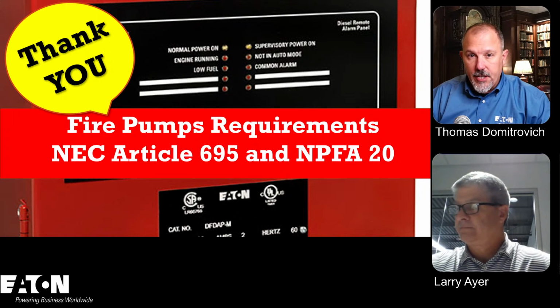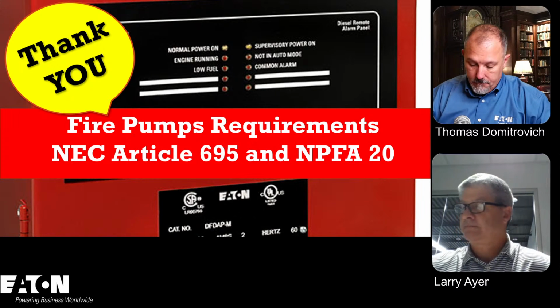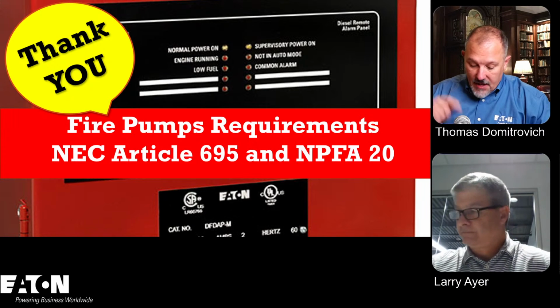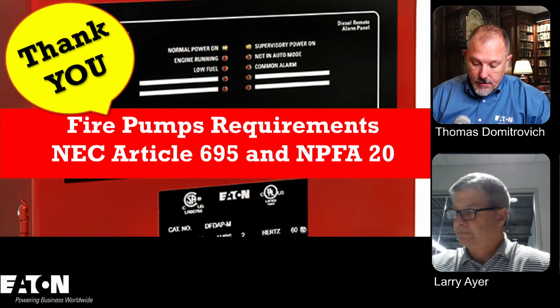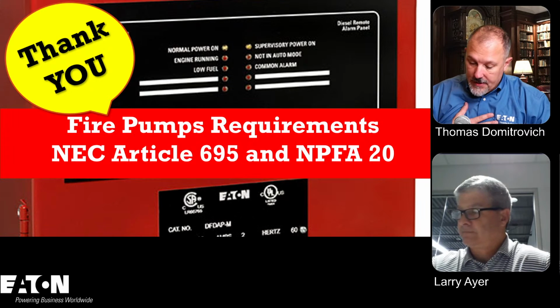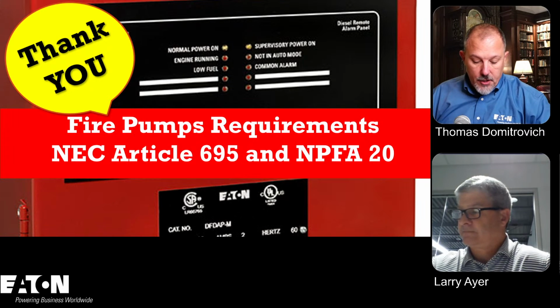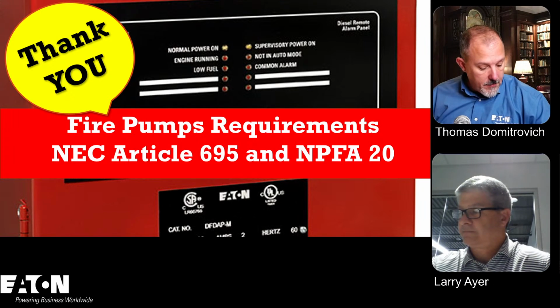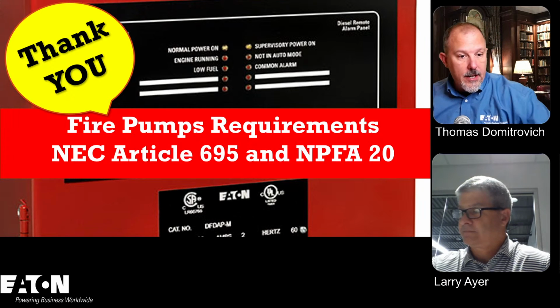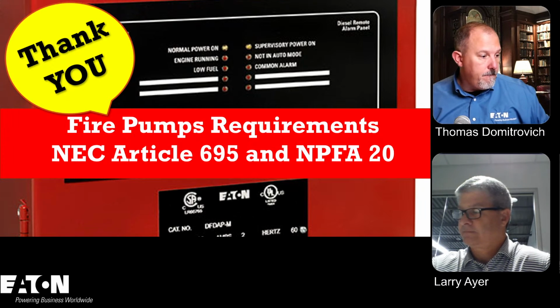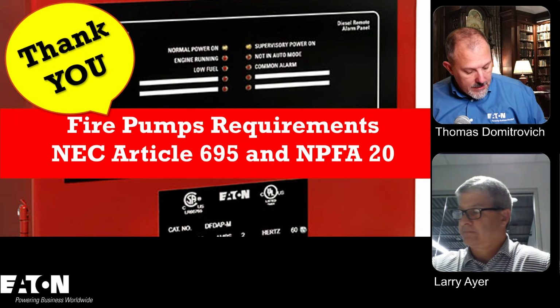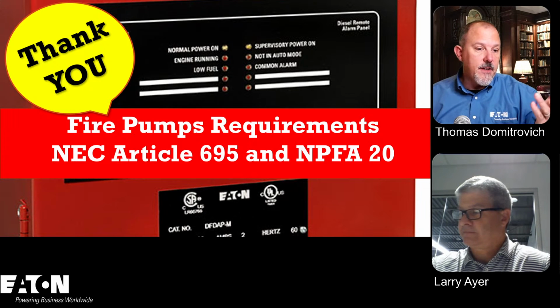So the transfer switch has to be in the pump room. That's interesting, but nothing in here says that I can find that it has to be listed for emergency use or listed for use with fire pumps. UL category code XNVE. So that's good. I've got to talk to Jeff Fecteau.